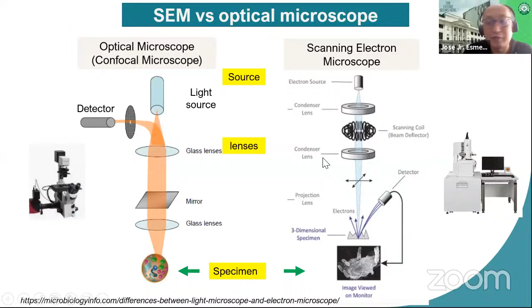Magnification in a scanning electron microscope is quite different compared to an optical microscope. It's defined as the ratio of the length measured on the SEM monitor to the length measured on the sample. The length measured is usually a scale bar located at the lower right of the SEM monitor. So images in a scanning electron microscope really depend on the quality and the size of the monitor. That's why in most images supplied to you from a scanning electron microscope, the scale bar is always present. It's not really the magnification, because the scale bar determines the resolution as well as the relative size of your sample or the object.